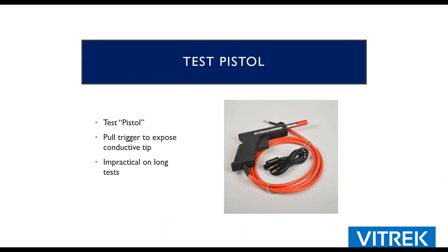So not everything has a power cord, obviously. Let's say maybe you're testing a printed circuit board or something like that that has a trace that you want to make contact to. For that, you need a probe. You wouldn't even be able to use an alligator clip. This test pistol style probe is probably your safest option. When you pull the trigger, the probe extends and you could use that with the hold steps or pause steps in the unit to make contact, maybe even a foot switch if you wanted to make sure that the operator was making contact, and then they could press the foot pedal and start a test. Highly recommend this product for anything that you cannot clip an alligator clip to.